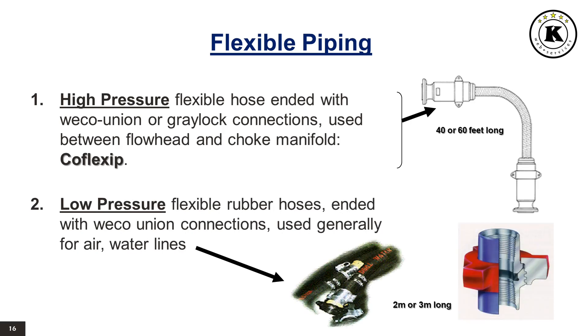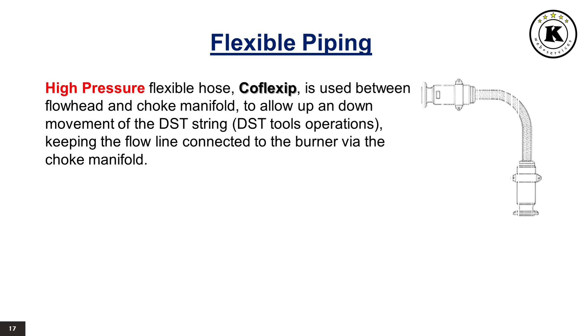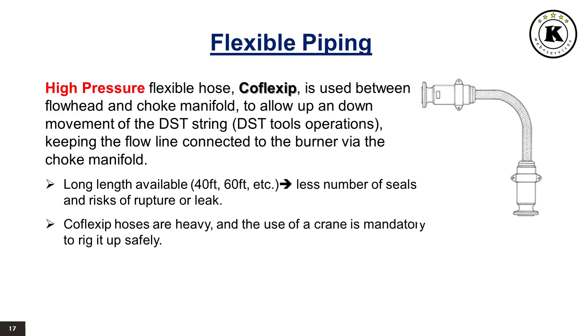Flexible Piping: High-pressure flexible hose, ended with Weco Union or Greylock connections, is used between the flow head and choke manifold — this is called CoFlexip. Low-pressure flexible rubber hoses, ended with Weco Union connections, are generally used for air and water lines. CoFlexip is also used between the flow head and choke manifold to allow up and down movement of the DST string during DST tool operations, keeping the flow line connected to the burner via the choke manifold. Long lengths are available — 40 feet or 60 feet — which reduces the number of seals and risks of rupture or leak. CoFlexip hoses are heavy, and the use of a crane is mandatory to rig up safely. To respect the MBR (minimum bending radius), a couple of elbows may be used at both ends of the CoFlexip hose.